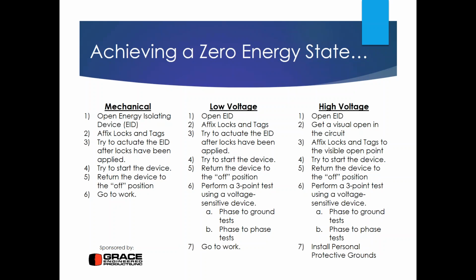Now, lastly on this slide, for those of you that might work on a wind farm or a solar farm, you have low voltage systems that are actually above 600 volts. You may have a 690 volt wind turbine. Some of the solar systems could have as much as 860 volts. They are constructed as low voltage systems, so you're going to use low voltage protective procedures with them.